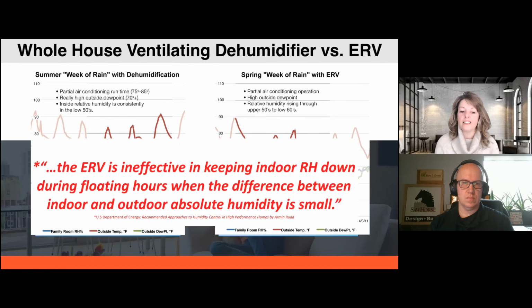And there was a study done by Armin Rudd for the DOE. And basically the conclusion was the ERV is ineffective in keeping indoor RH down during floating hours, which is going to be your morning, overnight times, when the dew points are high, and then the shoulder seasons when the difference between indoor and outdoor absolute humidity, so the dew points, is small.